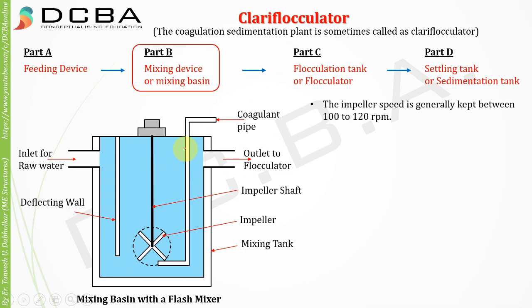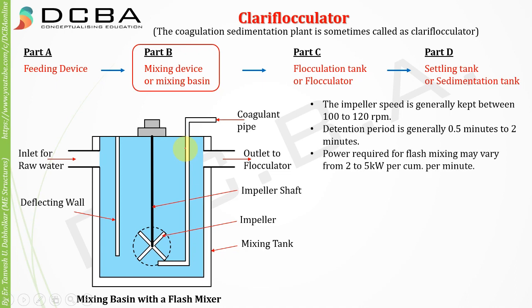The impeller speed is generally kept between 100 to 120 RPM. The retention period is generally half a minute to 2 minutes — very short for this kind of mixing basin. The power required for the flash mixer may vary from 2 to 5 kilowatts per cubic meter per minute.